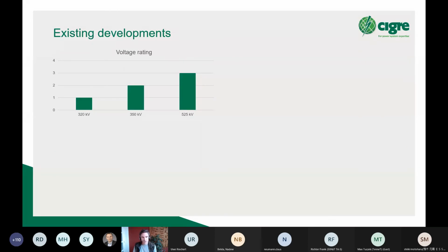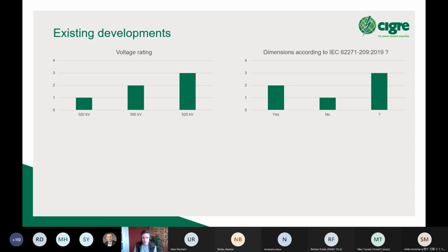We carried out a survey to find out what is already on the market, and a first feedback on the survey is, for example, about the voltage ratings, that there's quite clearly two different voltage classes, so to speak, one around 320 kV and the other one around 525 kV. So we will consider both voltage classes. Then another one, and this question also came up earlier in the presentations, is about the dimensions that are used in the design of the cable connection assemblies. So for AC, there are standard dimensions defined in the IEC 62271-209, and we asked the manufacturers if they follow the same dimensions, and some of them said yes, but interestingly, some also said no, and they have their own bespoke dimensions for their cable connection assembly design.